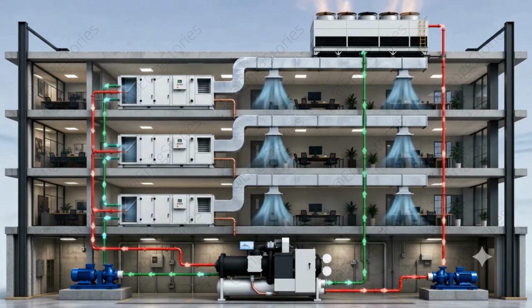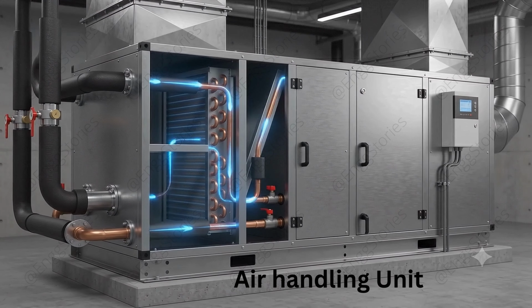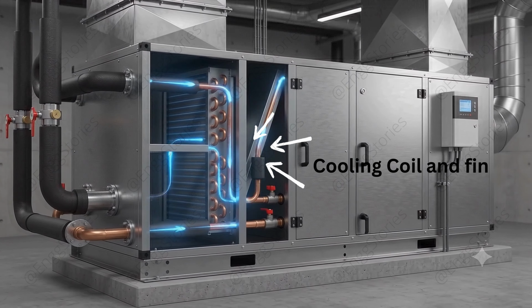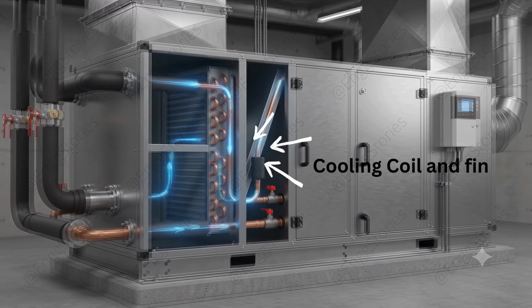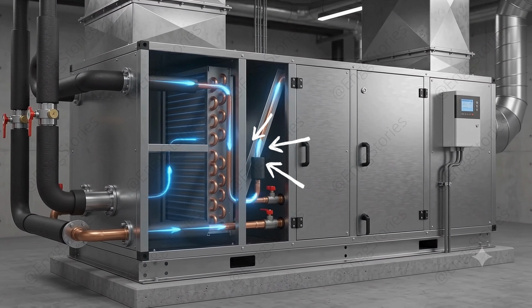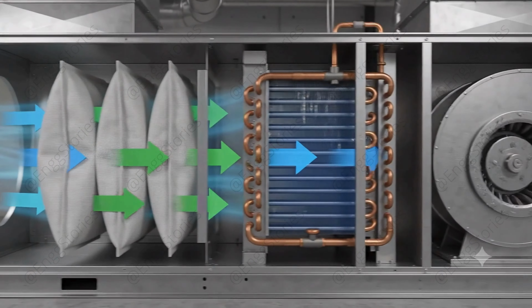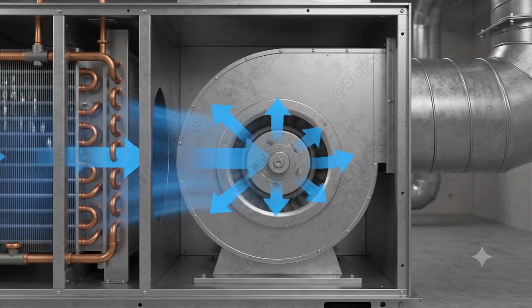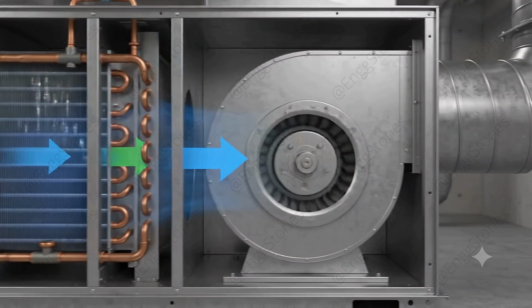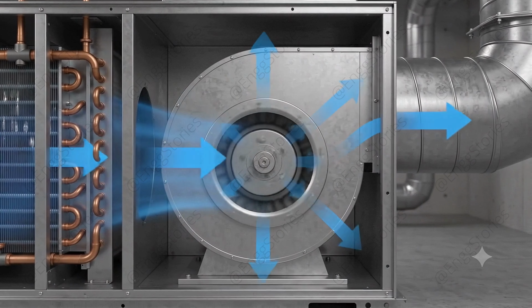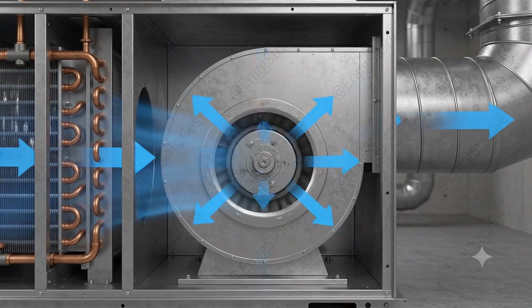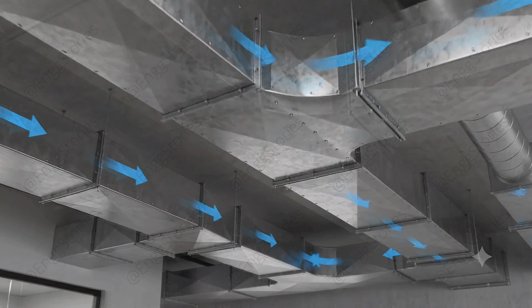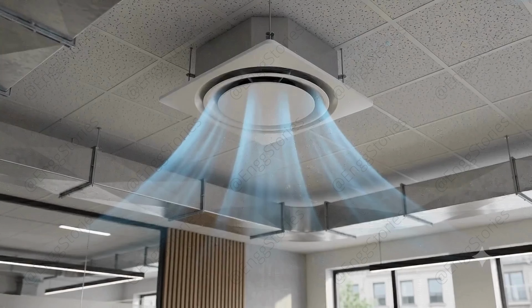A pump pushes cold, chilled water through insulated pipes to the air handling unit, or AHU. Inside the AHU, the chilled water flows through a cooling coil. This coil is made of many copper tubes with aluminum fins to increase the heat transfer area. At the same time, the AHU fan draws warm air from the building and pushes it across the cooling coil. As the warm air passes over the cold cooling coil, the air becomes colder. This heat transfer cools the air, and the air handling unit supplies this cooled air back into the rooms through the duct system, creating a comfortable indoor environment.